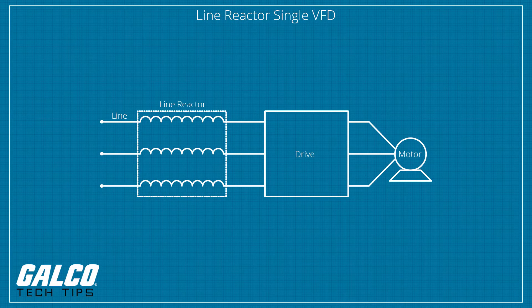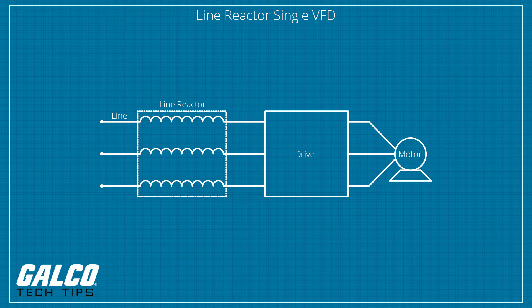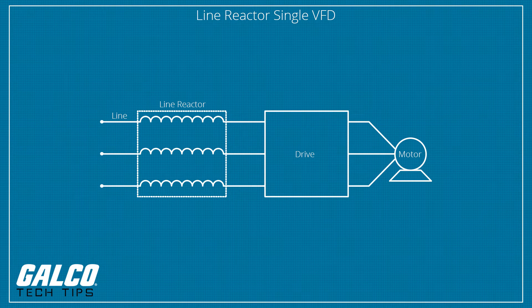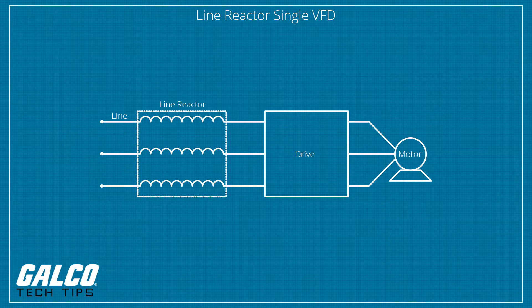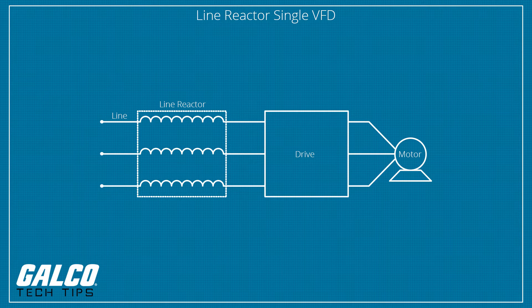However, drives that are running independently will require you to size a line reactor for the motor amps of each application independently.